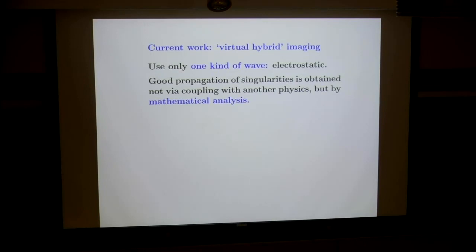And the reason you do that is because, of course, the body has its own naturally occurring electrical currents, heart and brain, for example. And you want to be in a regime which is totally unaffected by noise coming from the naturally occurring electrical fields inside the body. And so you do it in the tens of kilohertz range. And so that's not an issue.